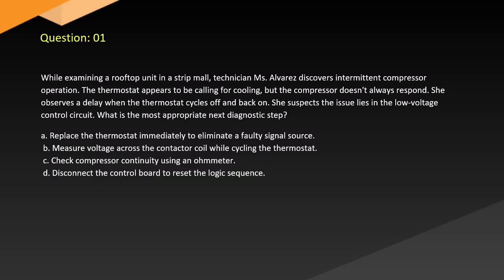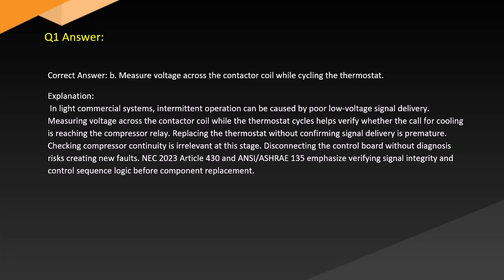A. Replace the thermostat immediately to eliminate a faulty signal source. B. Measure voltage across the contactor coil while cycling the thermostat. C. Check compressor continuity using an ohmmeter. D. Disconnect the control board to reset the logic sequence. Answer. Correct answer: B. Measure voltage across the contactor coil while cycling the thermostat.